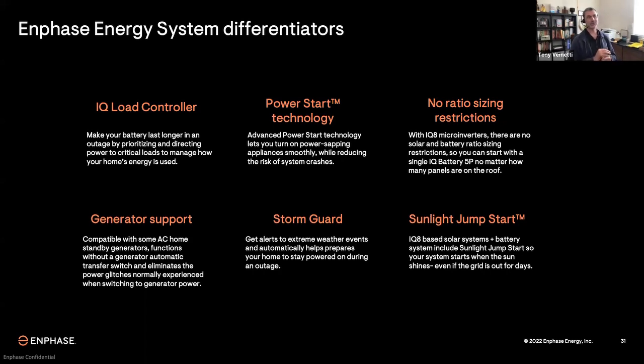No ratio sizing restrictions. So when using IQ8 microinverters on the solar array, you can install a very large solar array even with a small battery. With the previous generation of solar microinverters, the IQ7, and with other competitors on the market out there, you have to be really careful when sizing the solar array compared to the battery size. If you've got too much solar, it can be an unstable microgrid. So again, with the IQ8s, we've eliminated that problem. You can have as much solar as can fit into an Enphase system controller with any size battery.